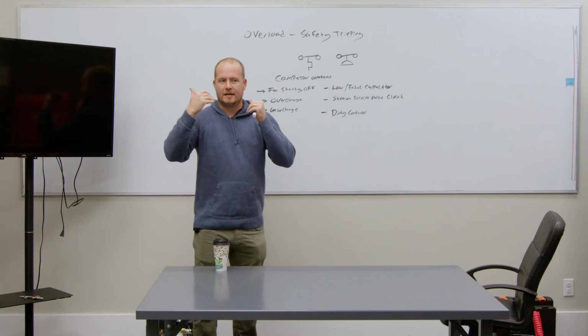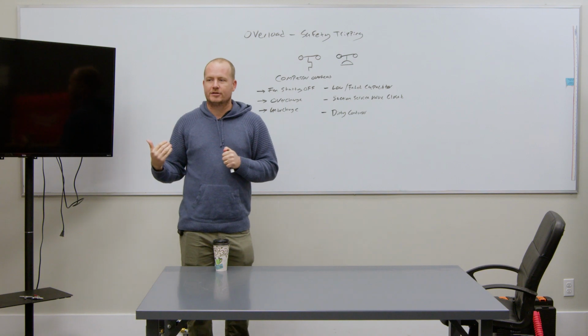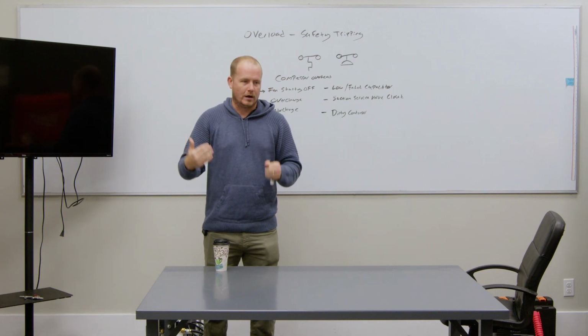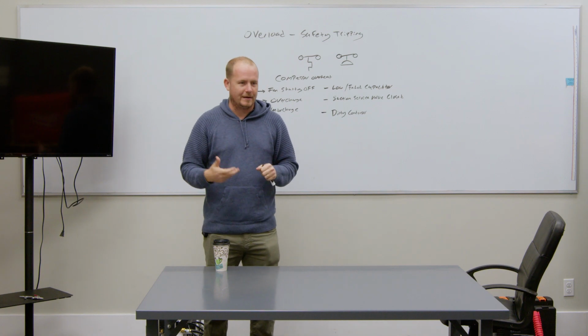Something caused that high pressure switch to trip. Now, for a newer technician, what are you prone to assume when you run into that circumstance? You walk up, it shows it's out on high pressure, the board's blinking codes, you reset the power, it comes on.